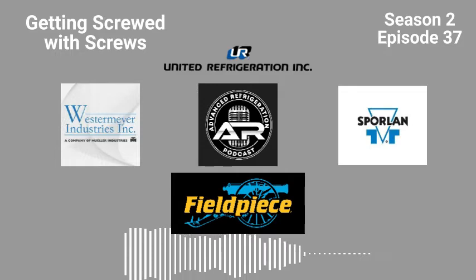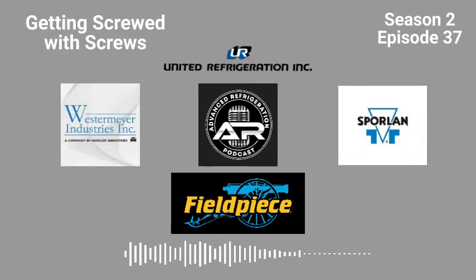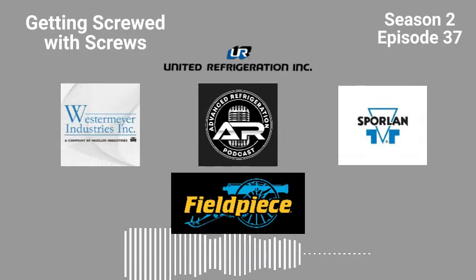Same store or different store? Same style stores, same style racks. These Carlisle oil filters are notorious for you getting a bath. Because what happens is there's a packed angle valve on the bottom of them, and when the filter explodes, it pushes the steel down of the filter all the way down against the bottom of the housing. So then it blocks the flow for the packed angle valve, rendering it pretty much useless.